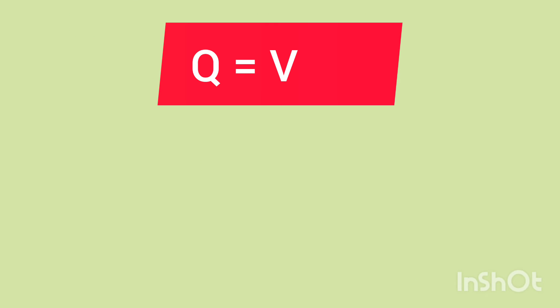So the basic formula for line sizing calculation is: flow rate equals velocity times cross-sectional area of pipe. That is Q = V × A, where Q is in meter cube per second, V is velocity in meter per second, and A is cross-sectional area in meter square.